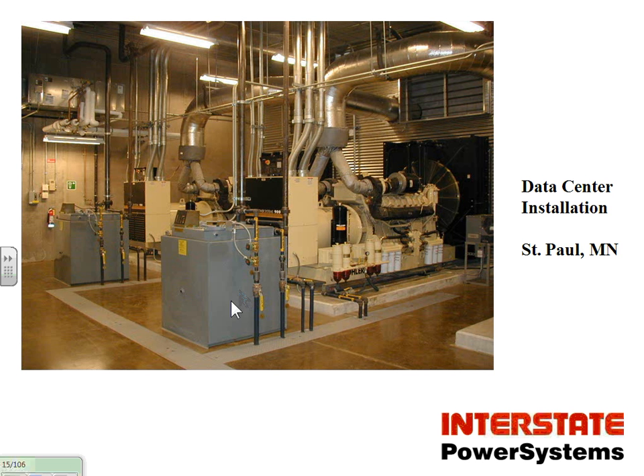This is a day tank here, and there's actually a third unit, so there's another day tank. There's a very large on-site fuel source here. You'll notice that over here on the generator set, we've got a set of oil filters here, a set of oil filters here, a set of fuel filters here, and another set of fuel filters here. That's a backup to a backup. Again, these are mission critical sets. They don't want them to go down, period. So they have many, many backups in place. That's just a couple of very common ones.